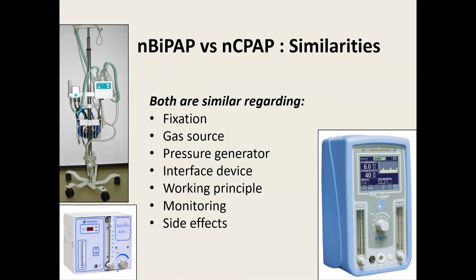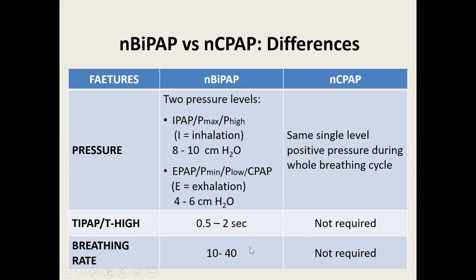However, they are different in certain aspects. In CPAP, there is a single level pressure during the whole breathing cycle, while in BiPAP, 2 level pressures are used, which are different in inhalation and exhalation. Their difference is generally 4 centimeters of water. In BiPAP, the time duration for inspiratory pressure varies between 0.5 and 2 seconds, while there is uniform pressure during the whole cycle in CPAP. Similarly, the breathing rate can be varied between 10 to 40 cycles, while there is none in CPAP.